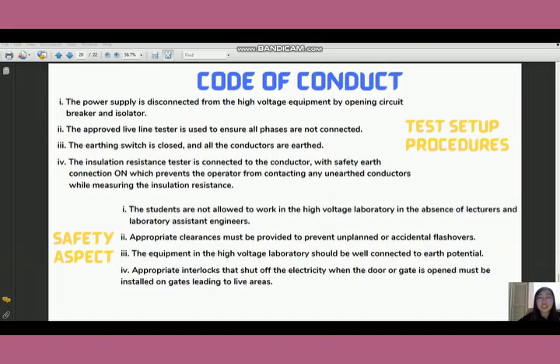For the safety risk assessment, in the code of conduct section, there are two parts that need to be discussed. The first is the test setup procedures and the second is the safety aspects. Here are some of the test setup procedures when conducting the lightning and switching impulse tests in the HV lab. First, the power supply is disconnected from the high voltage equipment by opening the circuit breaker and isolator. Second, an approved live line tester is used to ensure all phases are not connected. Third, the earthing switch is closed and all the conductors are earthed.